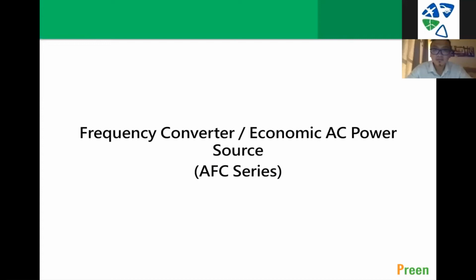Sometimes you have testing that needs to run at 400 hertz, so you need to convert from 60 hertz to 400 hertz, especially at airports. Most airplanes run at 400 hertz, so ground power units are all 400 hertz. You need to convert from 60 hertz to 400 hertz—that's true at all military and commercial airports.